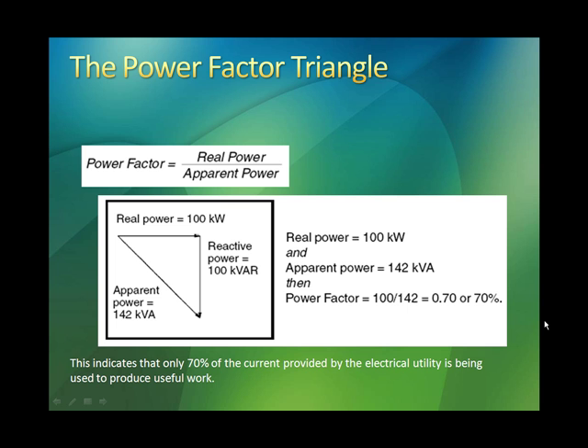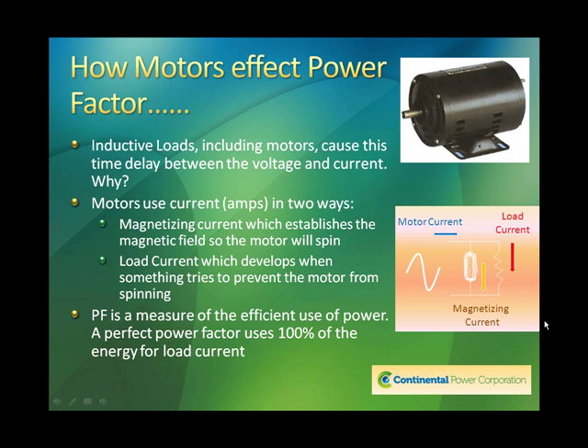The way we calculate, if we use some real-world numbers here, the real power of 100 kW, reactive power again is measured in kVAR, and the apparent power is measured in kilovolt amps, or kVA. In this example, the real power is 100 kW, and the kVAR is also 100. If you take those two lines geometrically, you can quickly calculate that the apparent power is 142. You use the power factor formula of real power of 100 kW over the apparent power of 142 kVA, and we get the power factor of 0.7, or 70%. And this indicates that only 70% of the current provided by the electrical utility is being actually used to produce useful work. Now, let's take this into a practical application.